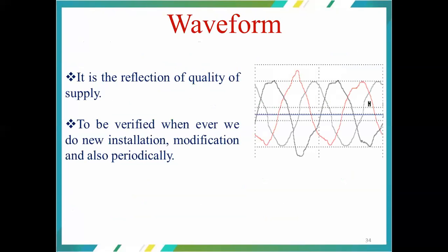And this is the waveform affected by harmonics. It is the reflection of the quality of the supply, like the temperature for the human body. The waveform shape is going to decide the quality of the power supplied to the utility or to critical loads. And it is to be verified whenever we do new installations, modifications, and also periodically. So whenever we are going for any charging stations, IT loads or data centers, we are supposed to check the condition of the waveforms.